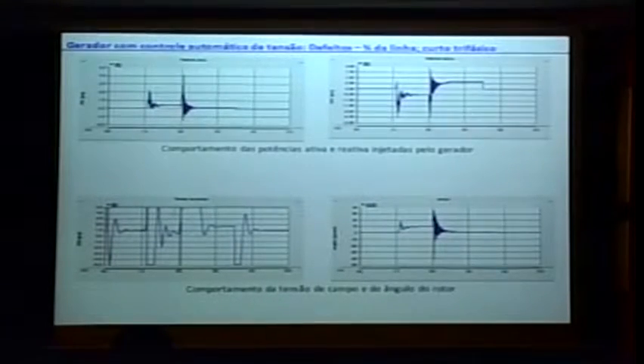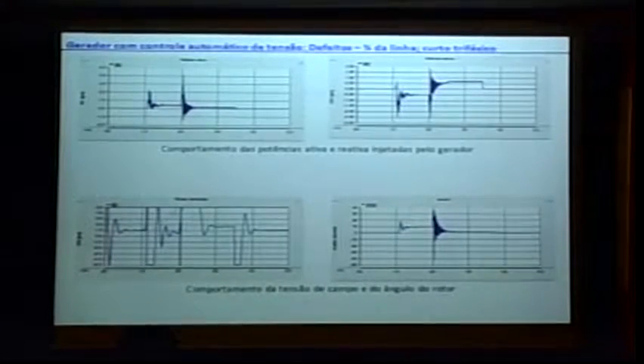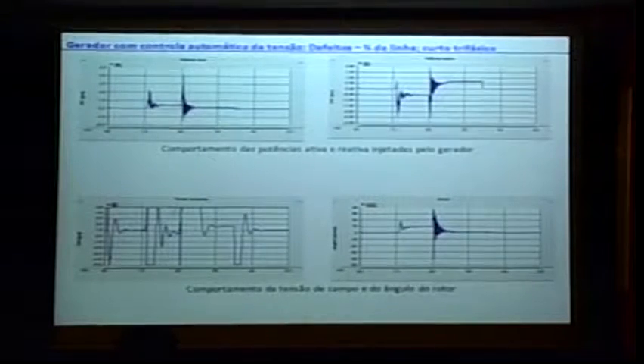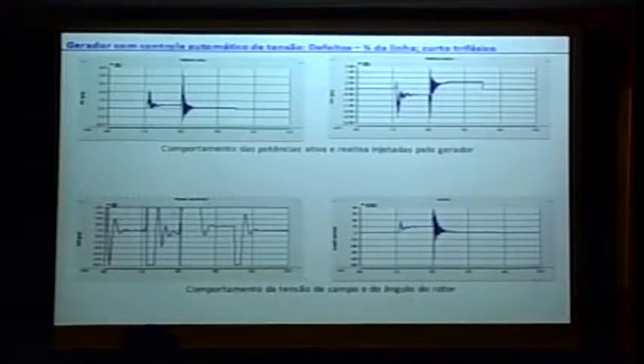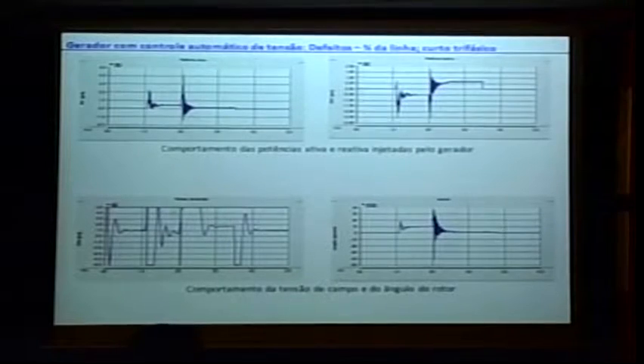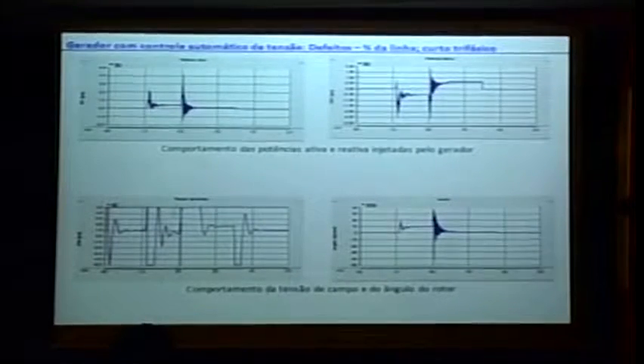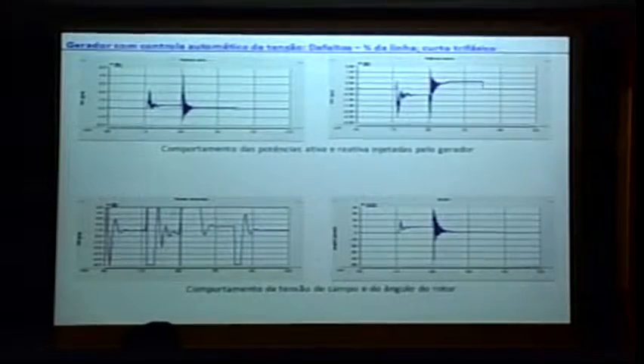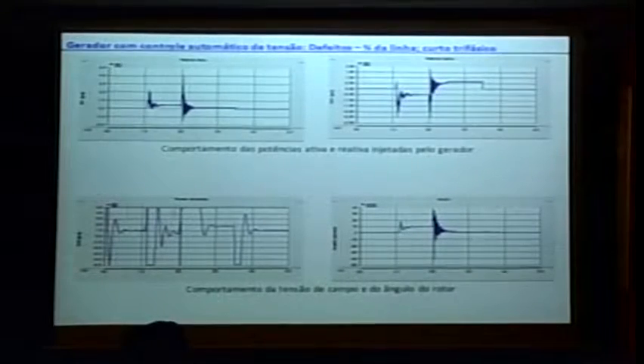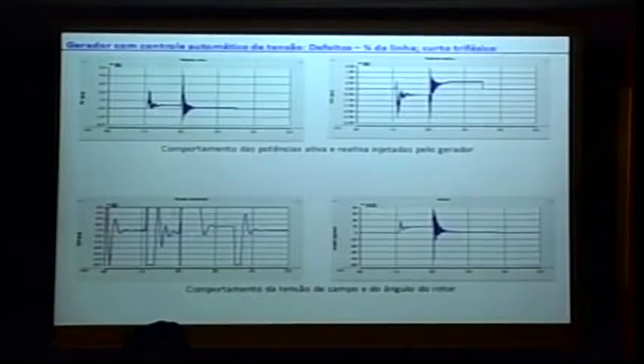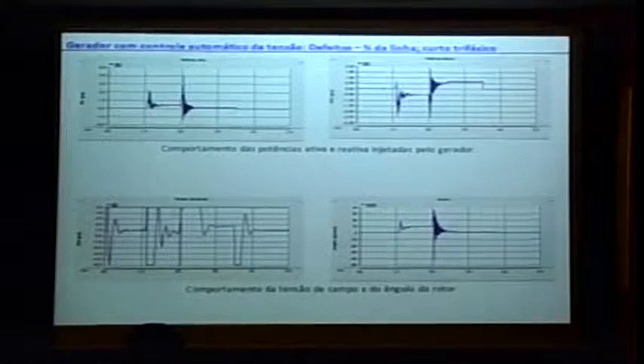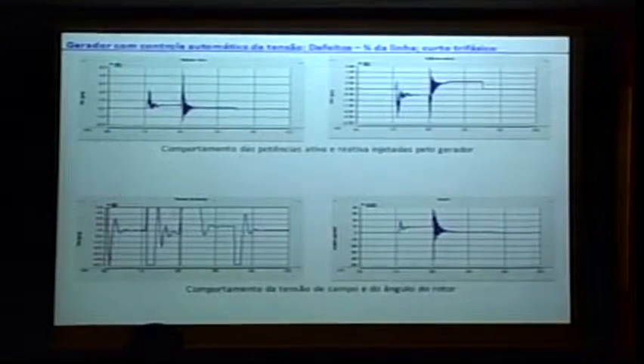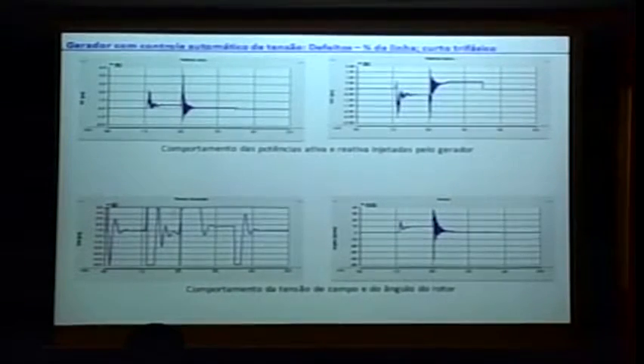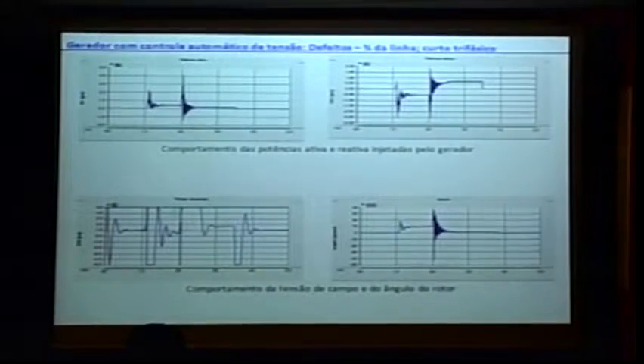So the quantity of active power that the machine is still providing for the line only of Serra da Mesa to Imperatriz diminished. But the reactive power grew a lot. So the machine was here, wait, it grew a little. It's around 0.6 pu of reactive power after elimination of the fault. The fault lasted 500 milliseconds. And here, all actuation of the AVR, here it can regulate the voltage. Here was still regulating. There was a short circuit. During the short circuit, the AVR cannot regulate the voltage.